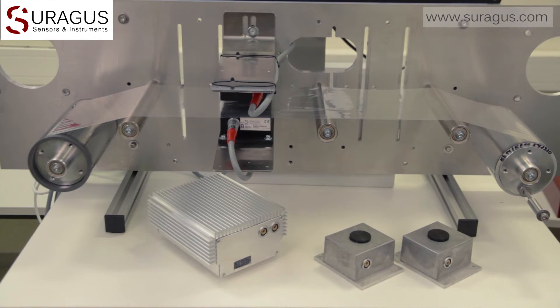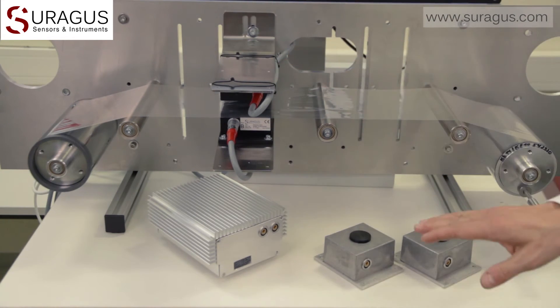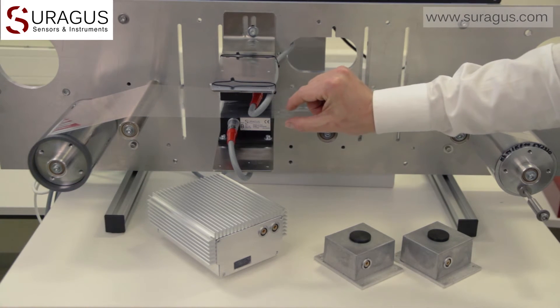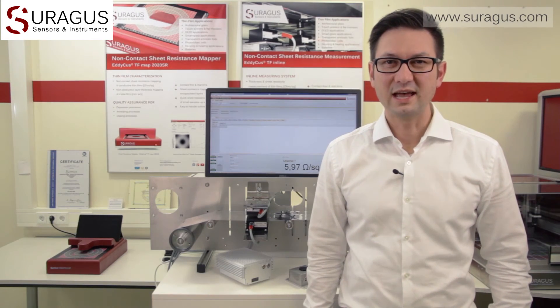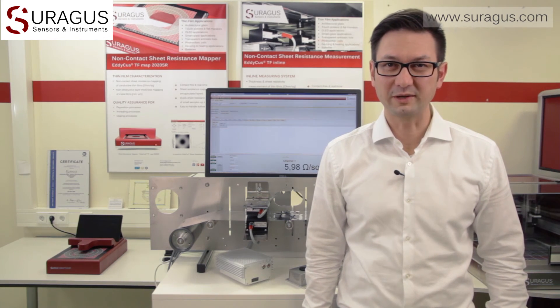The sensors can be applied at atmospheric pressure, as you see it here, or in vacuum like this set. The gap between the sensors can be adjusted between a few millimeters and up to 16 millimeters. Suragus inline sheet resistance measurement sensors are very helpful for a huge set of different quality check and process control applications.